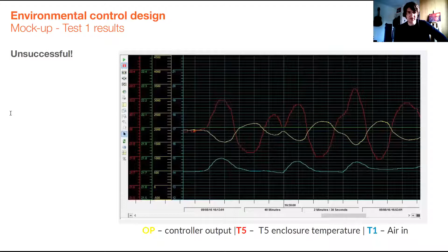So we looked at what was not quite right about it, and one of the key things we found was that we weren't getting a very good mix of temperature in the air. We were getting different temperatures at different points in the system, and we felt that was because the heater battery we provided wasn't delivering a uniform amount of temperature into the airstream. You can see the photo on the left hand side. We had this quite crude probe type heat battery, which wasn't delivering uniform heat into the airstream. So we changed that with a new coil, which was a bit more advanced, had a bigger coil, much more spread around the duct and the airstream, so it would deliver a more uniform amount of heat into the duct. And also we increased the coil's output size, because the system was struggling to do what we wanted it to do.